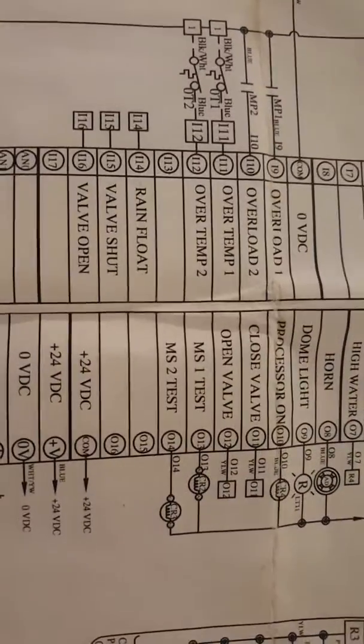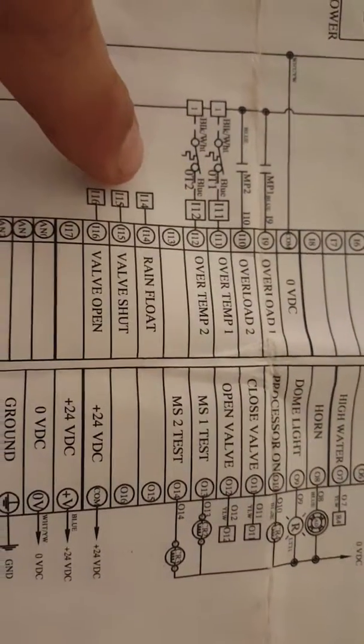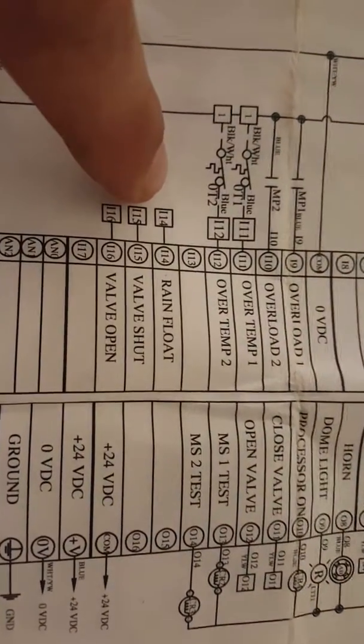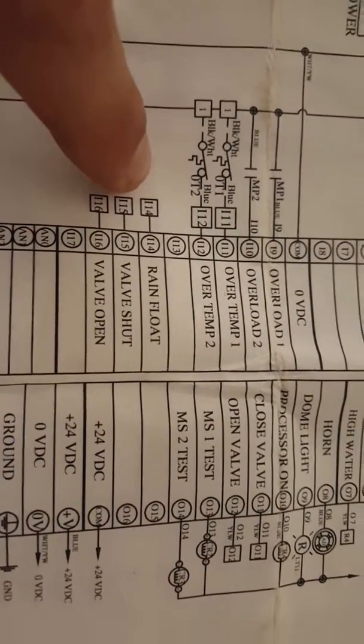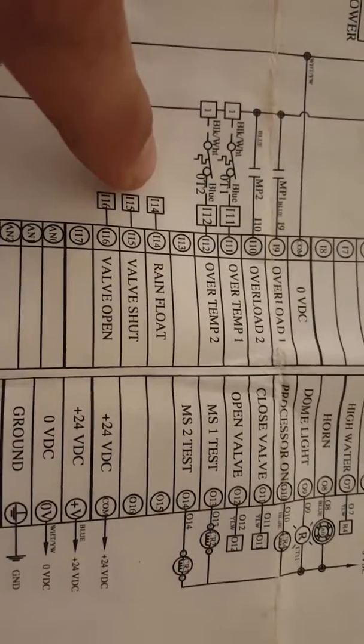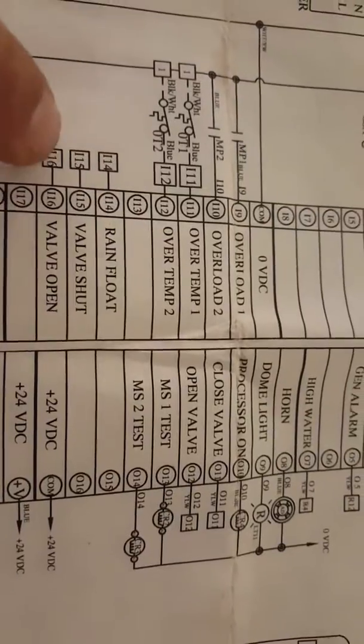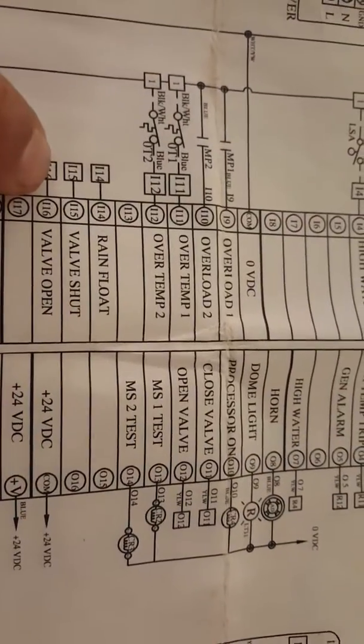Okay, so the way this system's supposed to work is we have a float installed outside in the sewer, and it's a normal open float, and it's tied into input 14. Now, if that float should close, indicating that water level has risen in the sewer, what's supposed to happen is we send an output through output 11 to a valve out in the street that closes. Once the valve is closed, we're supposed to get an input back on 15 telling us the valve is shut.